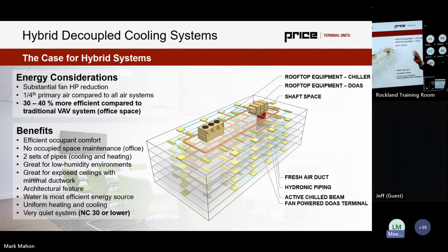Now, the case for the hybrid system and using both of these together, so we're going to have the same core duct layout completely. We're going to have very similar piping. So whether that's a 2-pipe hot-cold changeover or a 4-pipe system, we're going to run the same type of circuitry, the same type of loops. The only difference is maybe some consolidation of equipment with the DOAS box and a few less endpoints potentially.